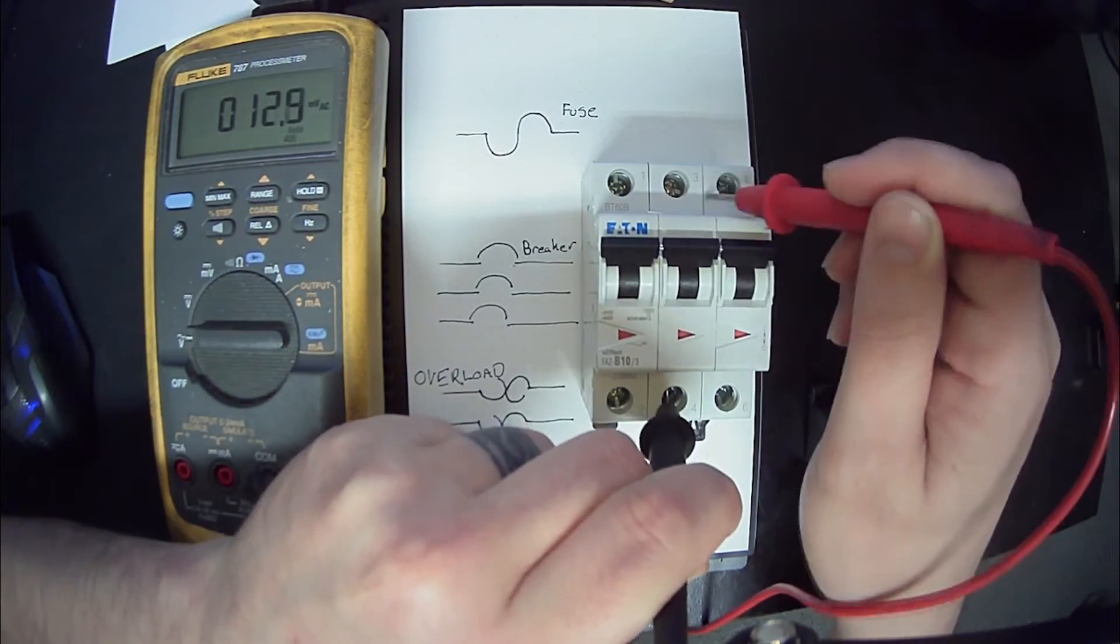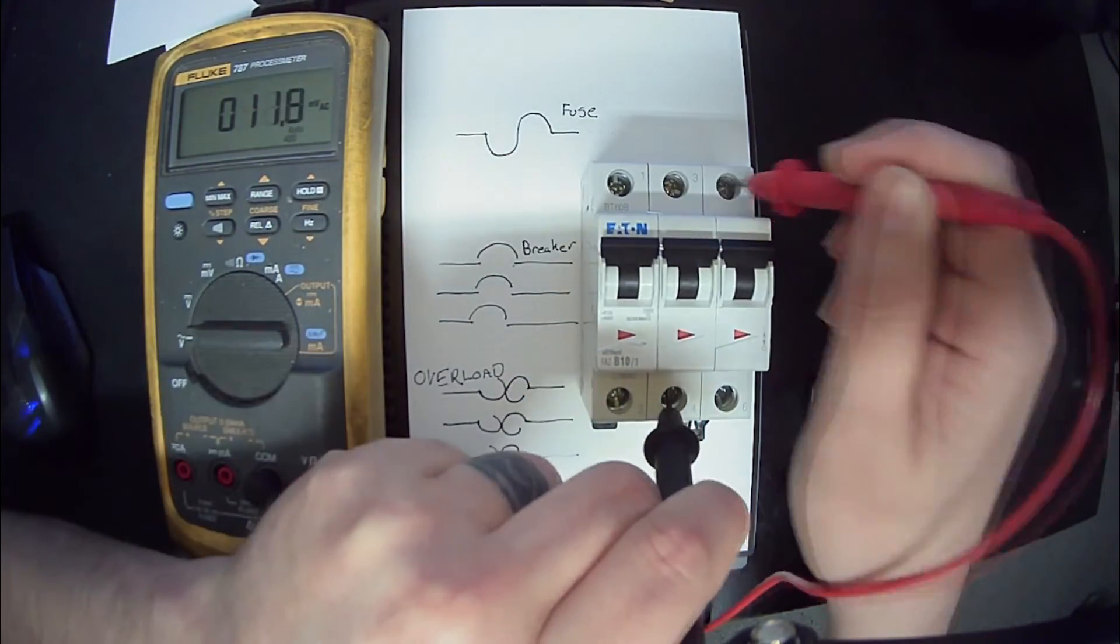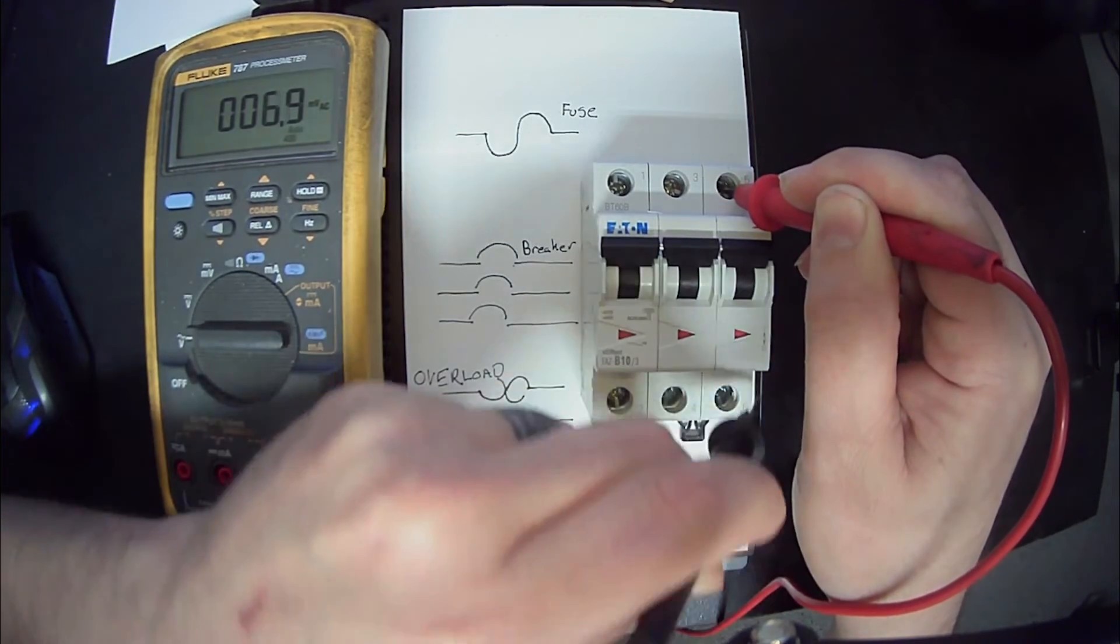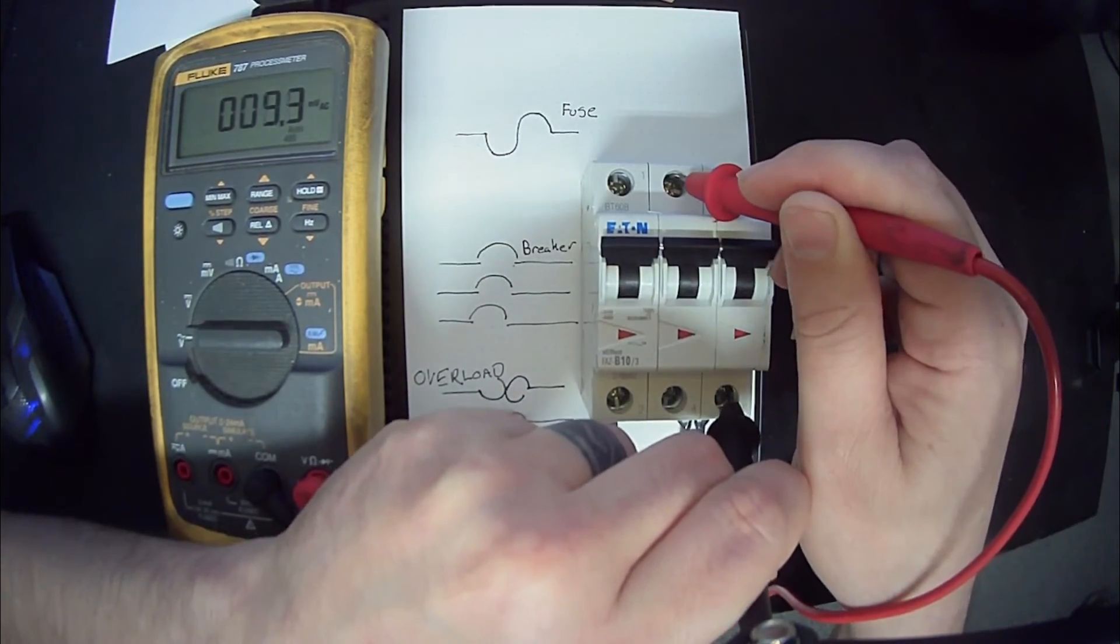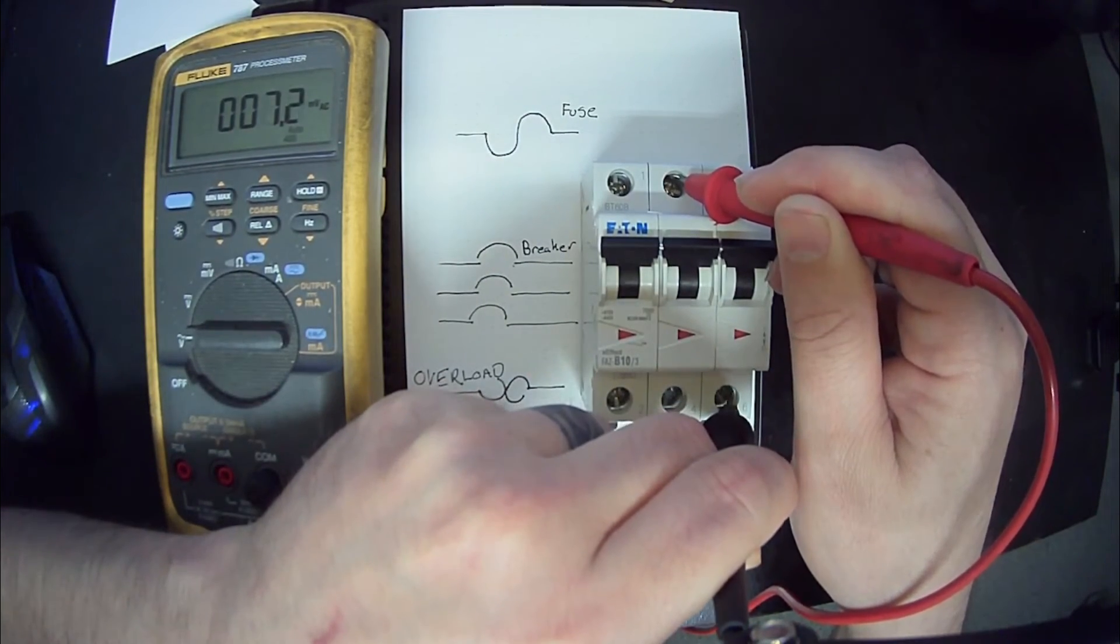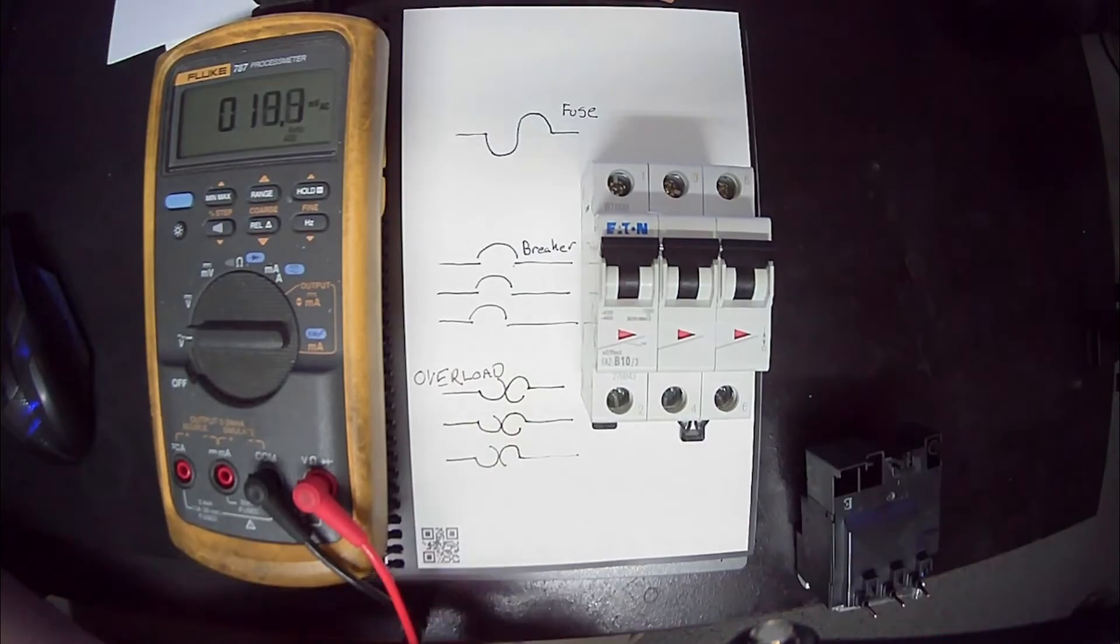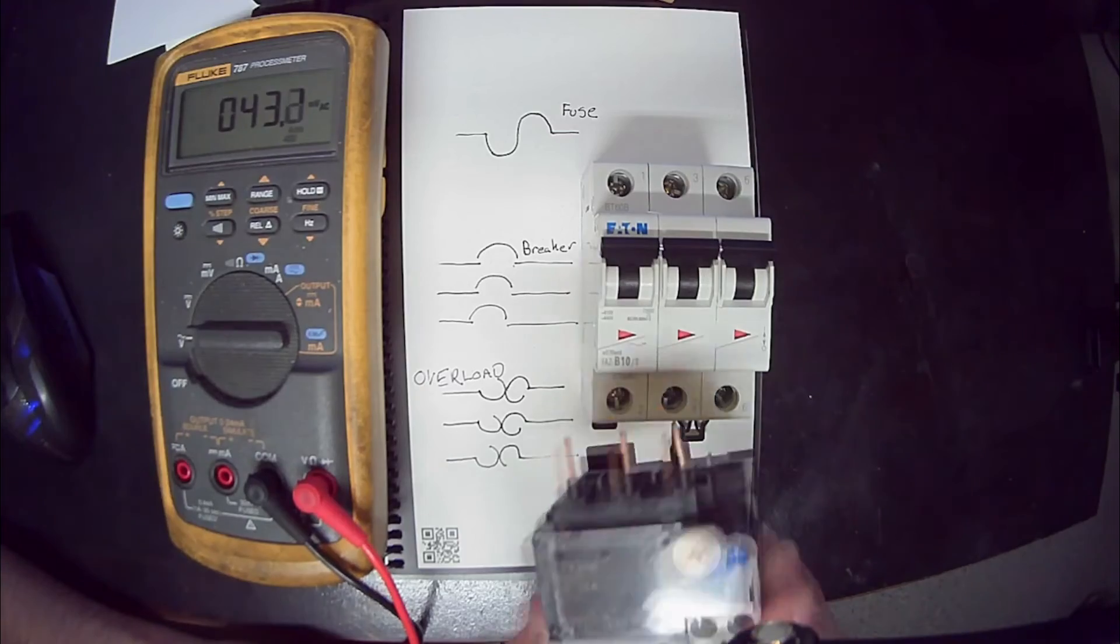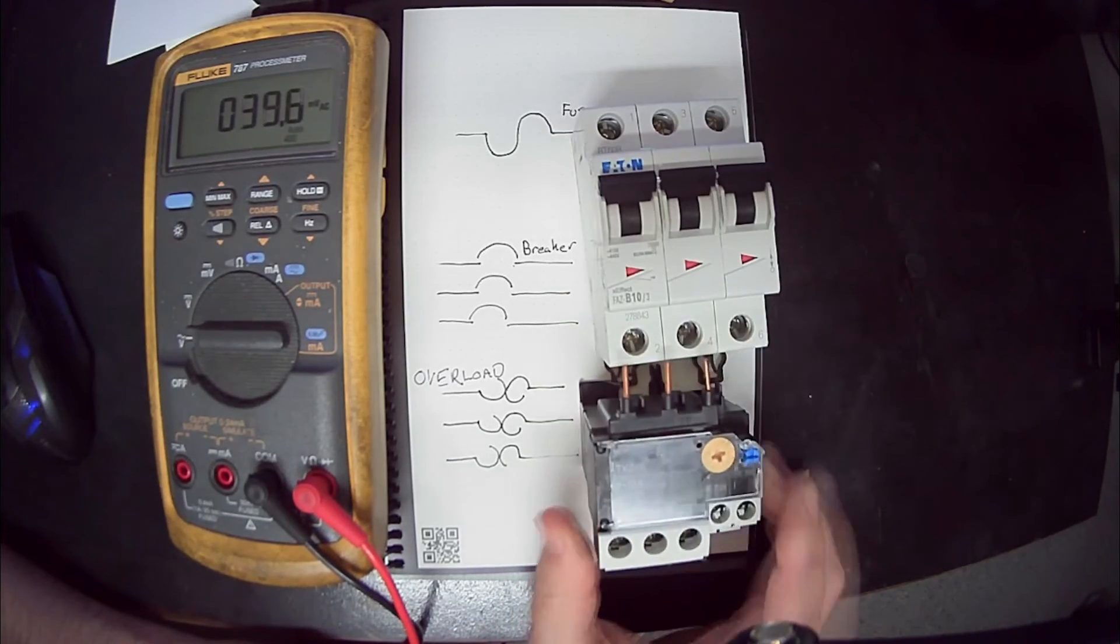If when I move to here, I have to move this lead to either here or here because I need a reference. So I'm going to move it to another spot. I'm going to test this one, I'm going to go here, I'm going to move this to a different spot because I'm wanting to test all three of these. And I'm going to look and see if I've got 480.